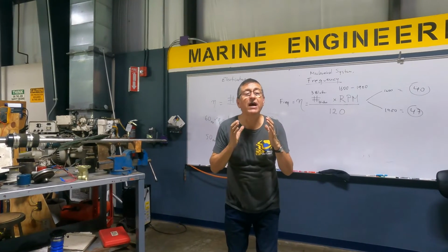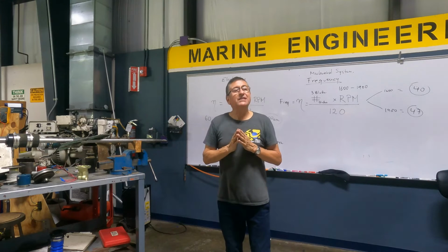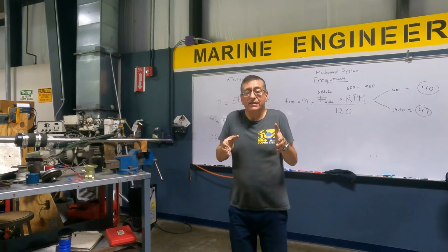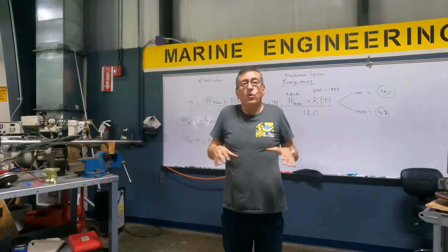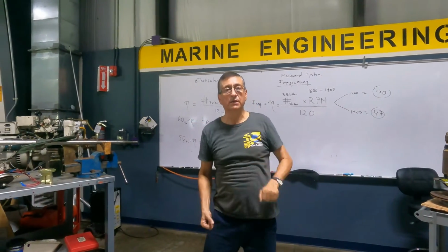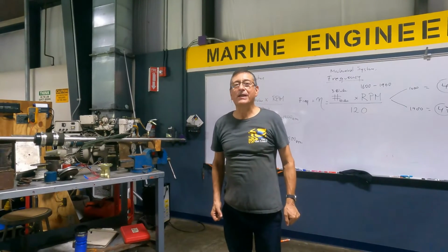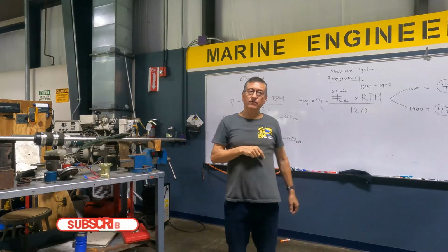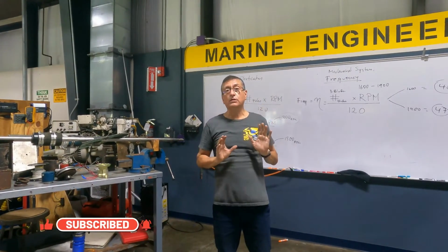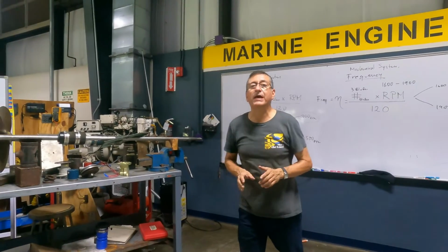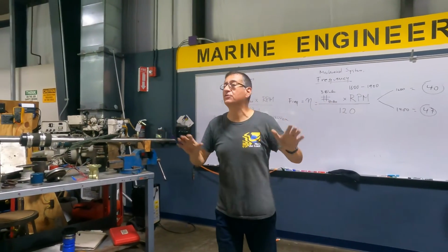This is the meaning of harmonic distortion. This is why the generator should be located in a place other than over the area where the propeller is located underneath. This is recommendation number 1. The installation is professional, but the location is not good. We need to move that generator to another place where it doesn't produce harmonic distortion.